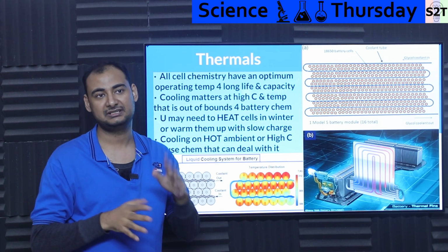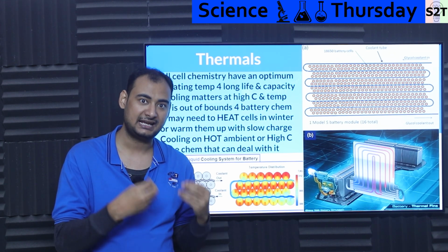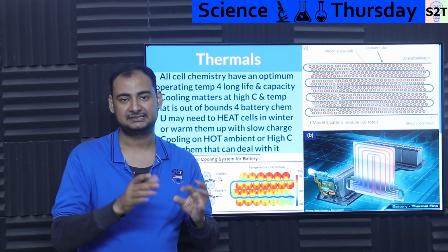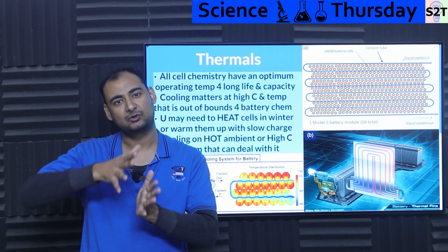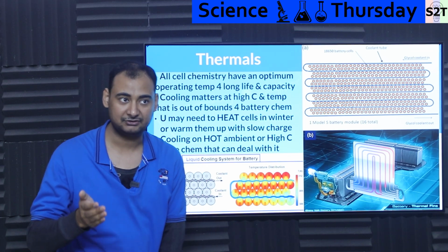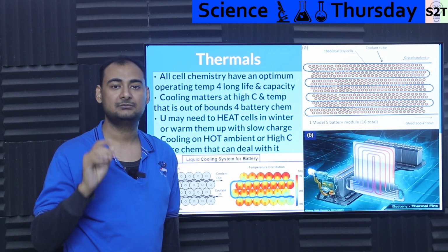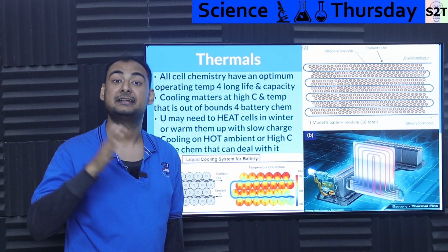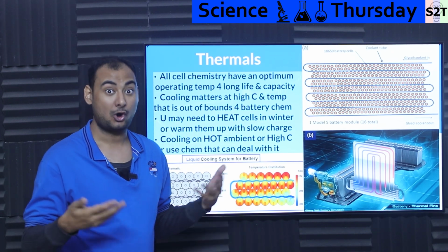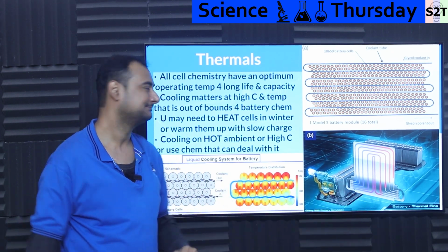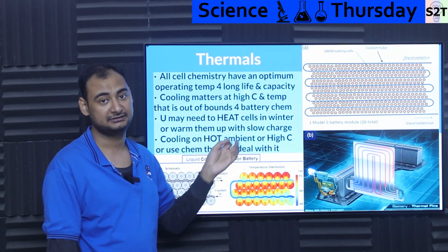Or again, if the chemistry is a bit different, when you are designing your own cell chemistry, you can ask the manufacturers, like, hey, change the sauce for a hot environment, and they can make it so that the cell is a bit more warm biased. You will have a penalty for that, but it will be healthy in that environment, meaning let's say if the capacity goes down, that's okay, but the 2000 cycle count will remain at higher elevated temperature. It can be done. Again, that's why we have chemistry options, select your option. So operating temperature, you have to maintain it for cycle life and capacity.